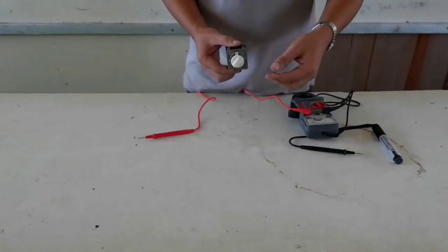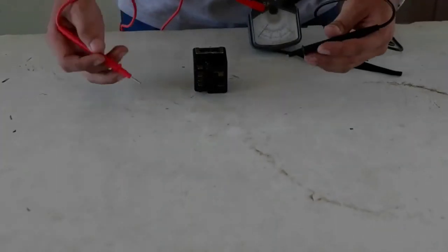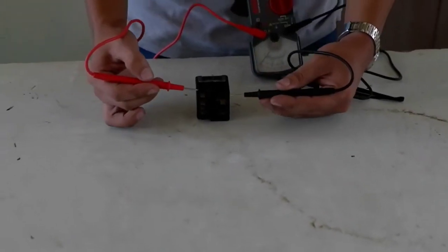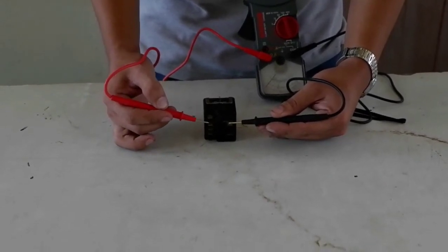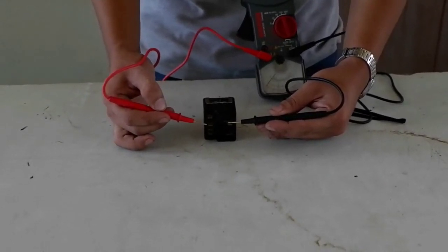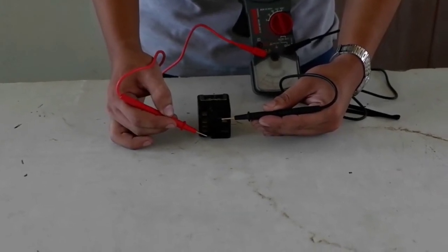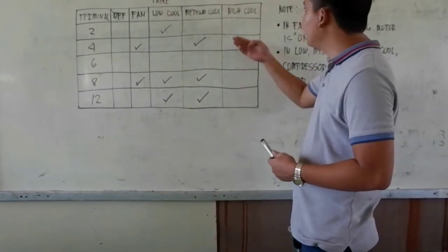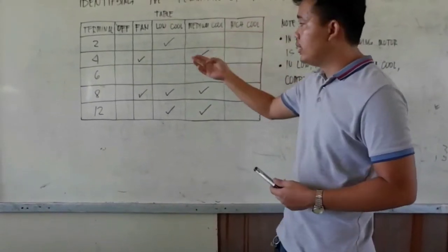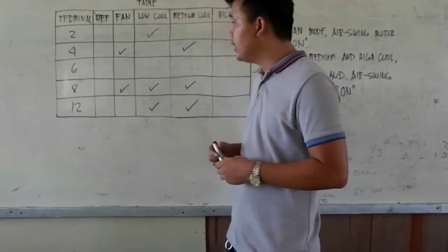Lastly, in high cool, we rotate the knob and test for deflection in each terminal. Terminal 2, no deflection. Terminal 4, no deflection. Terminal 6 has deflection. Terminal 8 has deflection. Terminal 12 has deflection. So in high cool, terminals 6, 8, and 12 have deflection.